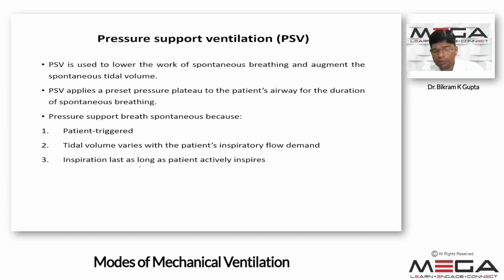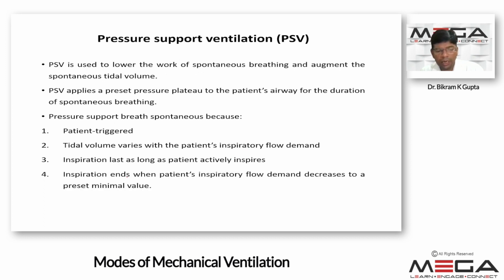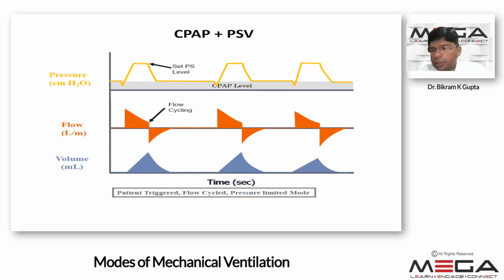Inspiration lasts as long as the patient actively inspires, and inspiration ends when the patient's inspiratory flow demand decreases to a preset minimal value. So we have to set the expiratory trigger sensitivity. If you are putting 60%, then when the maximum flow is measured as 100%, and the flow comes down from 100 to 60%, then automatically the cycling goes from inspiration to expiration, like here. So when the flow decreases from here to here, the inspiration goes into the expiration part. You can see here these are the scalars: pressure time, flow time, and volume time scalars.